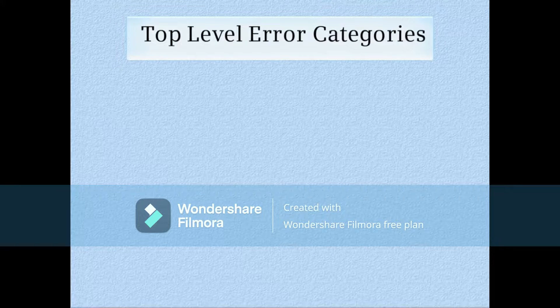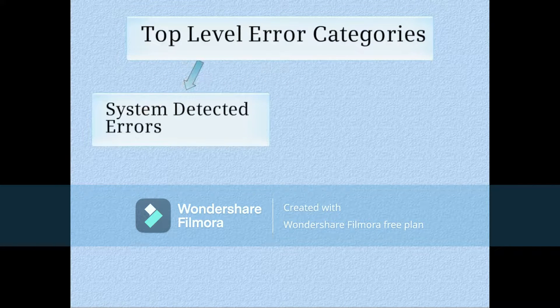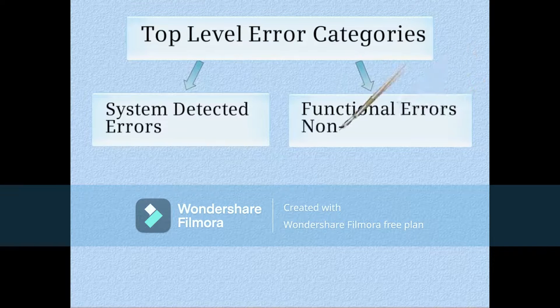At the top level there are basically two categories for errors: those that the system can detect, sometimes called stop errors, and those that the system cannot detect, called functional errors. System-detected errors will usually cause the CPU to go to stop mode. With functional errors, something doesn't work right but the system cannot detect what it is and the CPU does not stop.